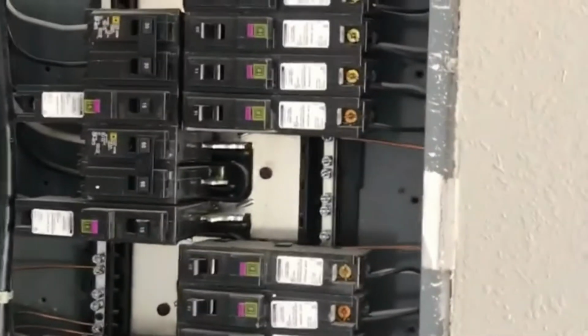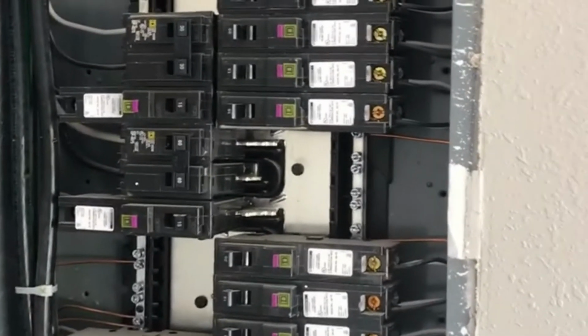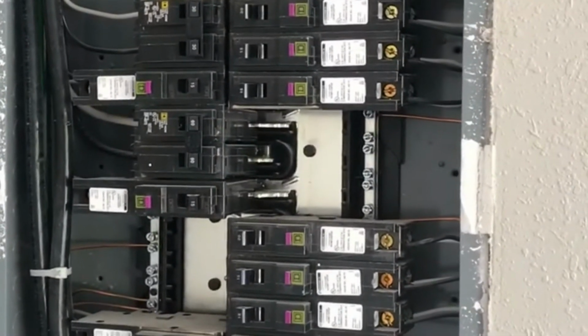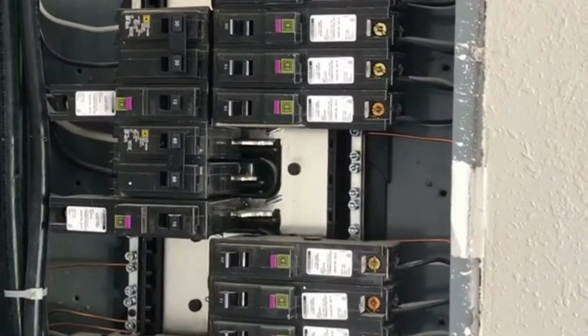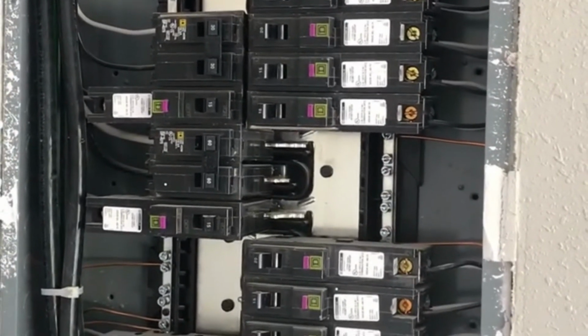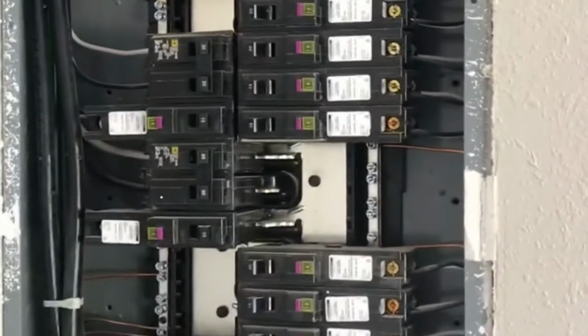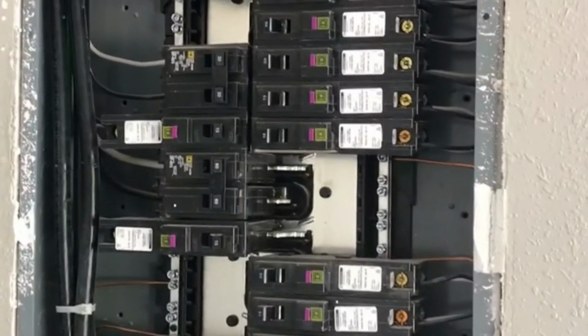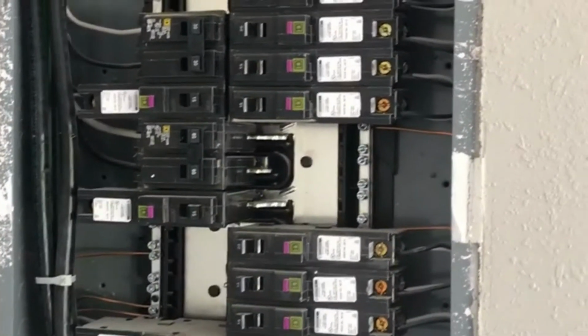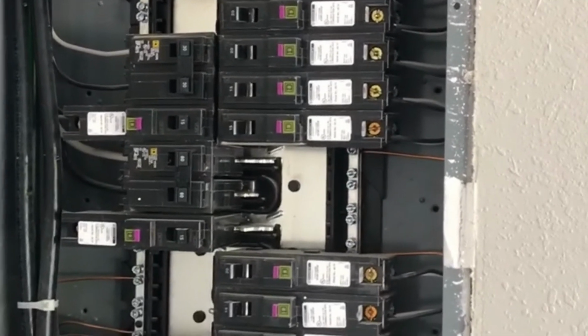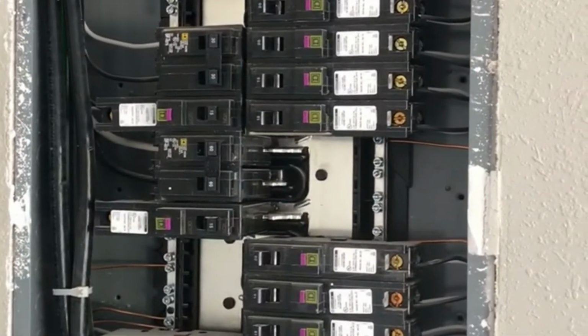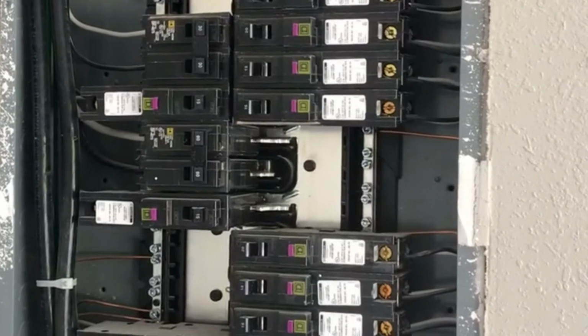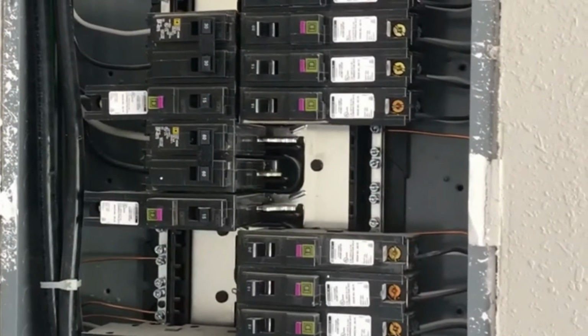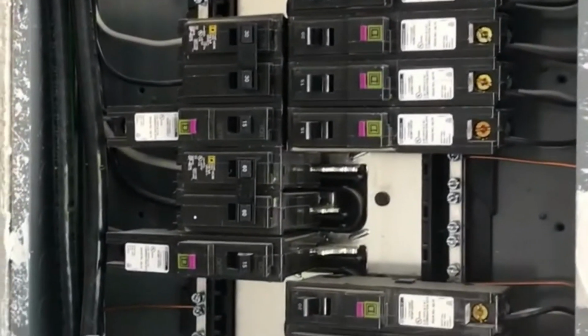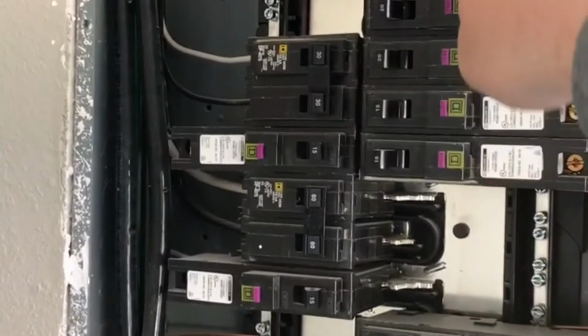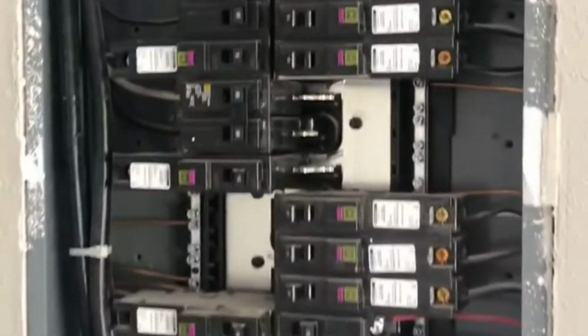The breakers in this breaker box are all arc fault ground fault breakers, which is required by Kentucky's electrical code. The arc fault ground fault breakers eliminate any potential fires from arc flashes from electrical components. They also eliminate, actually, the need to have GFCI outlets inside the house because the ground fault is controlled inside the breakers.